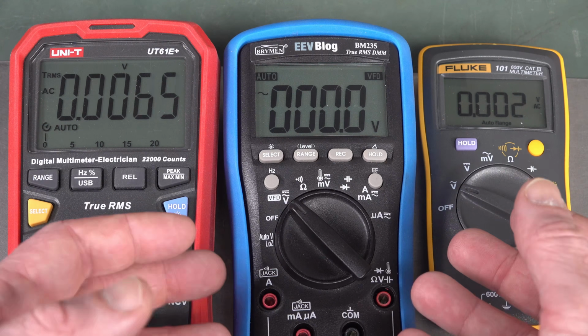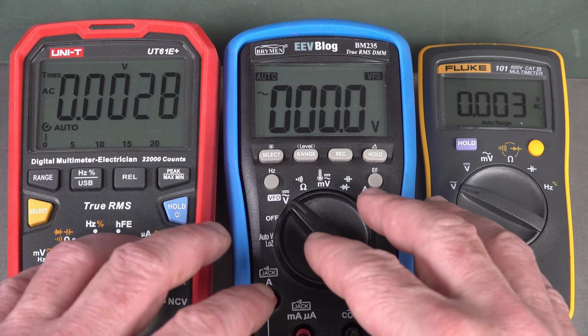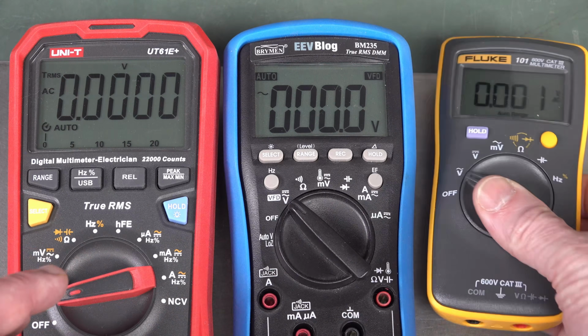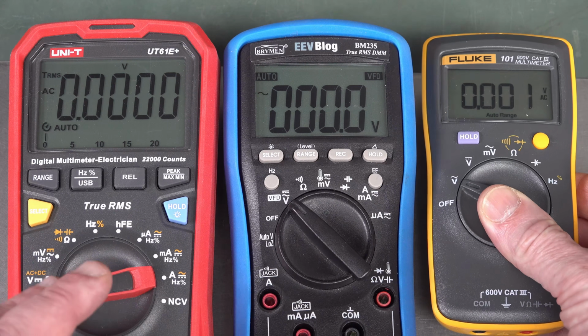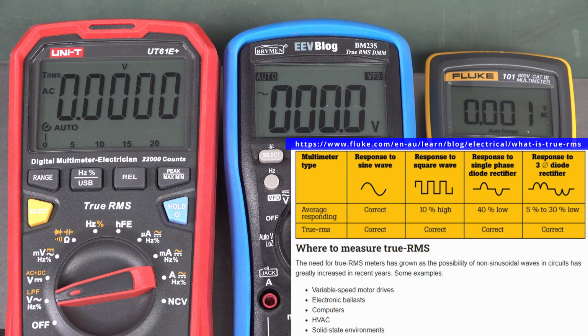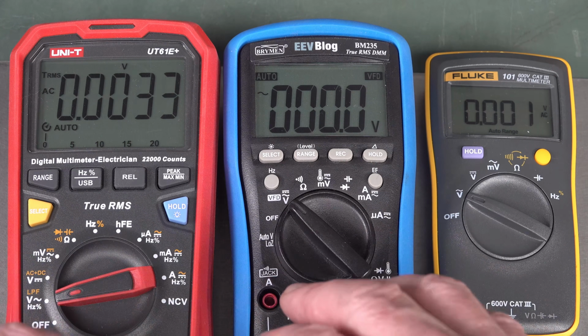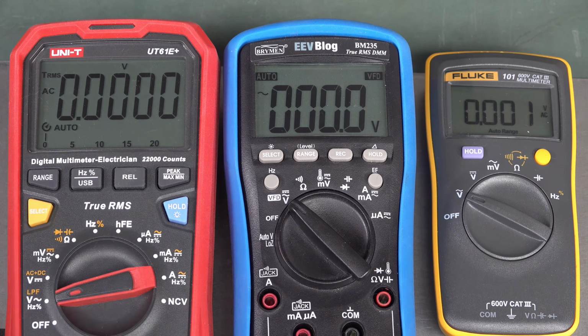If you're measuring AC voltage or AC current, and that's the only thing true RMS applies to, using a non-true RMS meter like this average responding one will only get you accurate readings for a complete sinusoidal waveform, like on your mains 110 or 240 volt power supply. Any other AC signal that's not sinusoidal won't be accurate, and that's where a true RMS meter will be more accurate. But for most purposes, if you're watching this video, true RMS is nice to have, but not really that important.